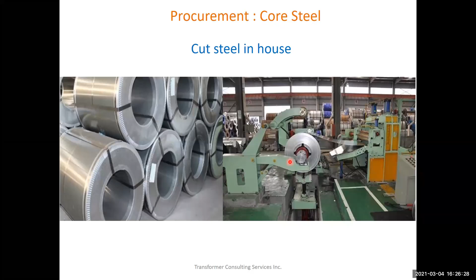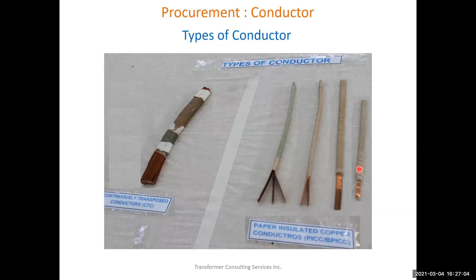So now here you see the type of conductors. On the left hand side, you have CTC, continuously transposed conductor. On the right hand side, you have that magnet wires, different kind of magnet wires that are being used in the transformer industry. The reason I'm showing you this conductor is because look at the conductor being wrapped with the gray thing. This gray thing is called insulation. This insulation is nothing but carbon hydrogen chain. This carbon hydrogen chain will absorb the moisture during the manufacturing process if the factory is not being climate controlled, which can compromise the quality of the transformer.